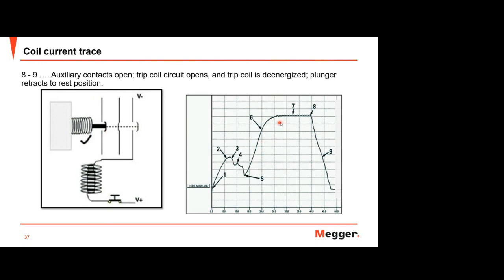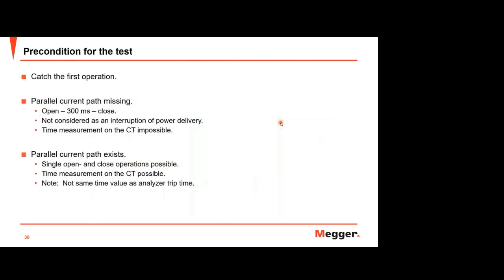So it is the main reason why we can trace it from this coil current. Yeah, this is the precondition. This is how to test. You just need to catch the first operation. If there is no parallel current path, meaning no parallel system, you can do just a reclose: open, give a delay of 300 milliseconds, and close. Then you can get the measurement. But if a parallel current path exists, if you have the parallel system, you can do just a single open and then see what happened, and then you can close again, because you have the separate system as backup.